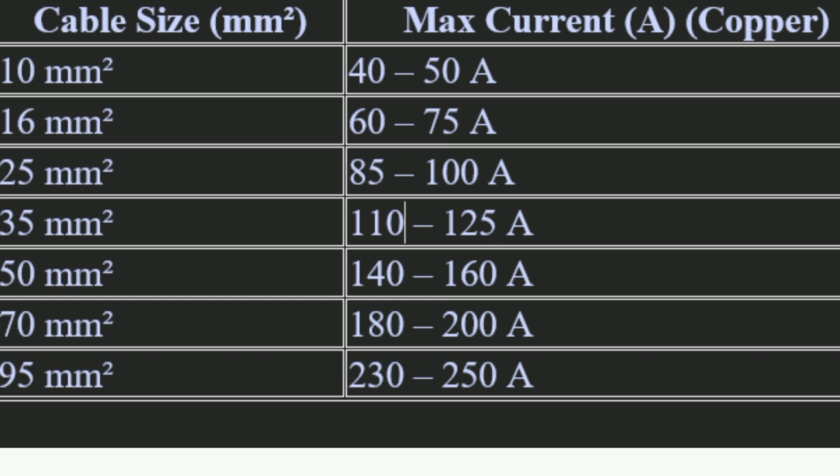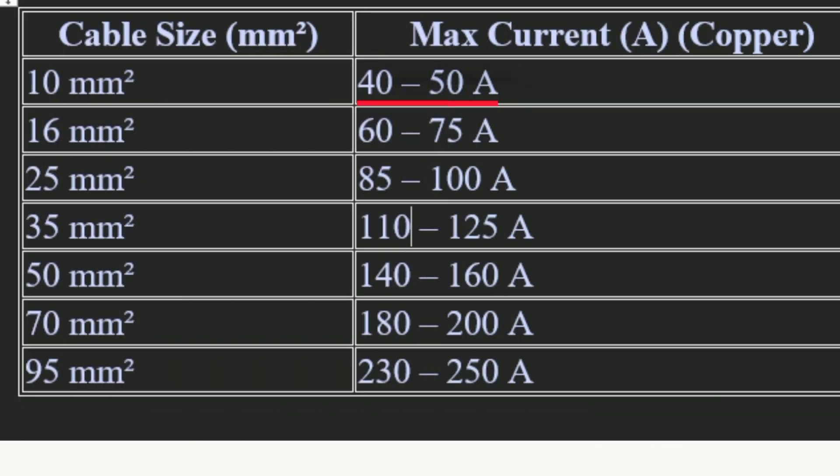Looking at the table, we have cable size and maximum current rating. The 10mm² cable has a rating of 40 to 50 amps. However, if a 10mm² cable is not high quality it may not carry up to 50 amps, while a high-quality 10mm² cable can. So you must choose quality cables, and other factors like ambient temperature may also apply.